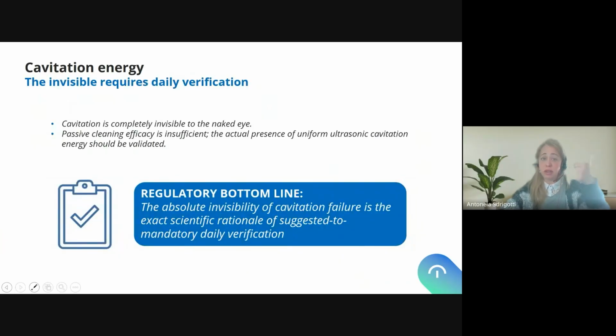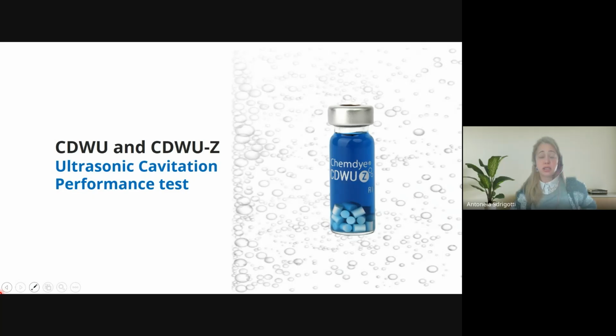So cavitation is completely invisible to the naked eye, as we have spoken. Passive cleaning efficacy is insufficient, so the actual presence of uniform ultrasonic cavitation energy should be validated. So the regulatory bottom line is that the absolute invisibility of cavitation failure is the exact scientific rationale for suggested to mandatory daily verification. So what is the solution that Terragen has developed in order to make this monitoring very simple, very straightforward? It is the ultrasonic cavitation performance test, for which we have two different options. We have the CDWU and the CDWU-Z.